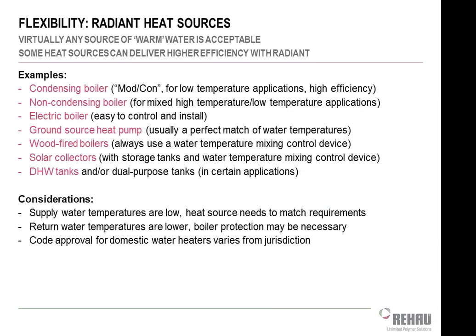Additionally, if you have a 95% AFUE rated boiler, that's what it is at its design conditions, which are probably, whatever, 140-degree return water or something like that, or 160. If I run that with lower water temperature, the efficiency actually goes up. So many times you'll have a 95% condensing boiler that's actually behaving like a 99% condensing boiler when you slap it onto a radiant system. So you do even get a higher boiler efficiency because of the lower water temperature. So not only do you save energy because you've changed the space temperature set point in your space, but you also save energy because you're operating the boiler in a condensing mode more frequently, which helps you out as well.